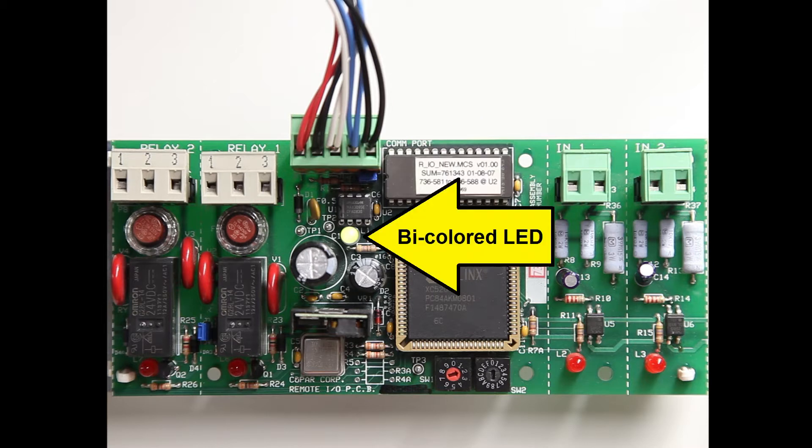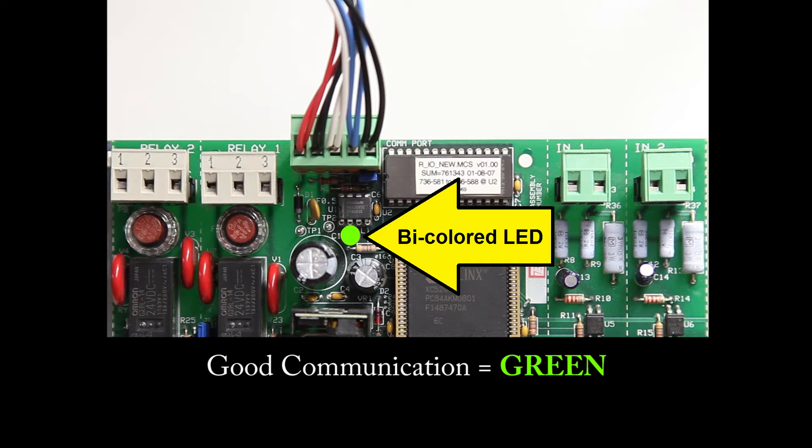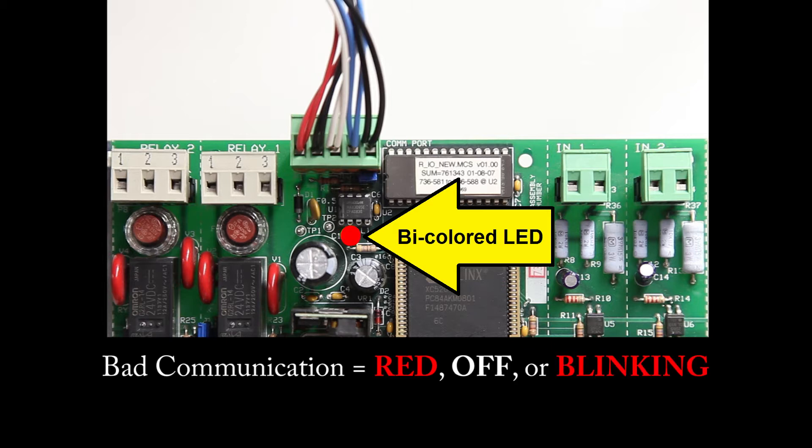This is a bi-colored LED, which indicates the status of the card's communication. Normally, the LED should be green, which indicates communication to the card is good. If the LED is red, off, or blinking, there is a communication problem. In this case, it is possible the jumper is in the wrong position.